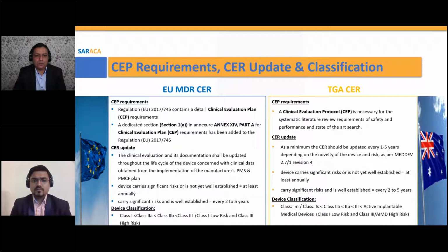If the device carries significant risk or is not yet well established, you're required to do it annually. That requirement also follows through in the TGA, which states that if the device carries significant risk or is not yet well established, you're required to update it at least annually. They're very similar in both jurisdictions; if it is well established, then you need to update every 2 to 5 years.